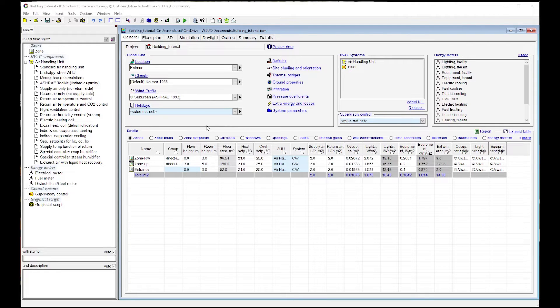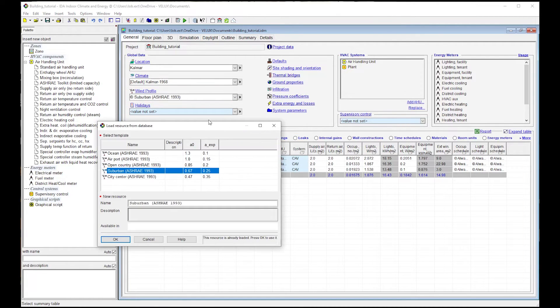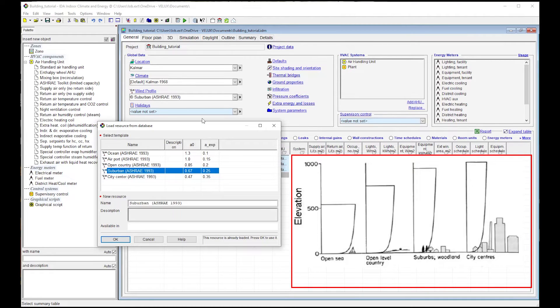Let's start with the first one – the wind profile or wind correction factors. You need to import a climate weather file which provides the wind speed at the height of 10 metres. The wind pressure at different heights can be determined by the terrain type, which categorises the airflow behaviour between buildings. From the dropdown menu, you can load wind profiles from a database. The different wind profiles are provided by ASHRAE. You can see different examples of wind profiles that show the difference of the wind speed gradient based on the surroundings, and choose a wind profile depending on the site context.